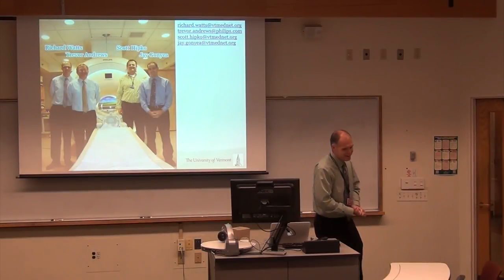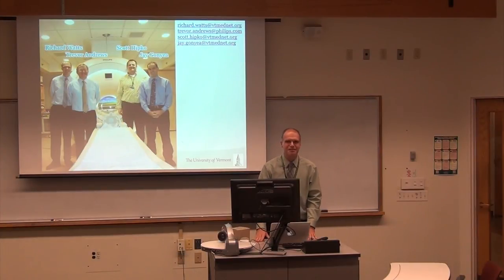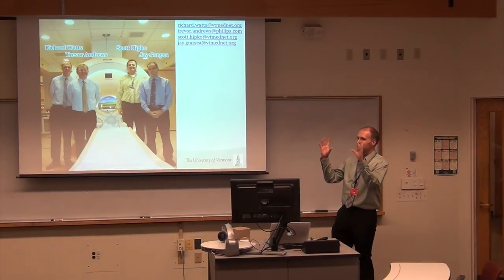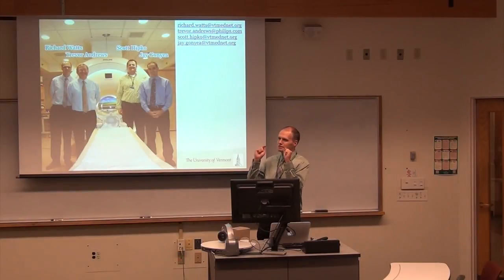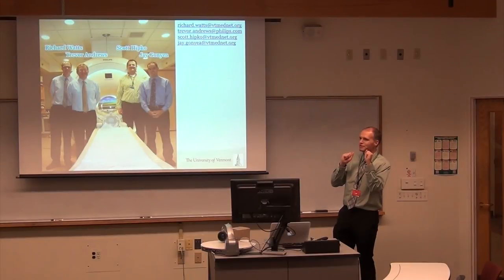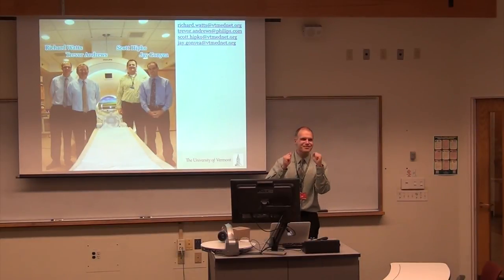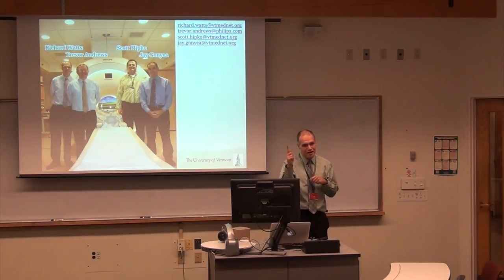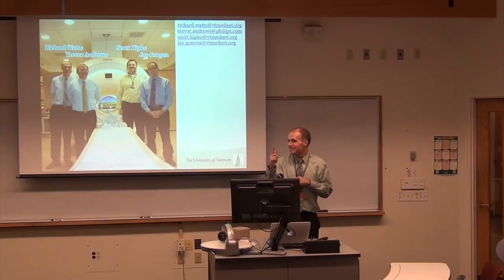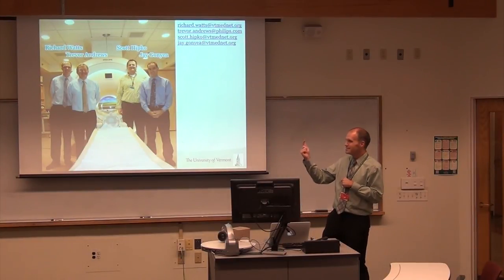Good question. Anybody who's sat in an MRI scan knows they are incredibly noisy. Actually our scanner can easily hit 130 decibels, which is very, very noisy. There are no moving parts in our MRI scanner - no moving parts. What do we have in an MRI scanner? We have a big magnetic field, and we have 3 gradient coils. We switch current through these 3 gradient coils very rapidly. What happens when you put a current through a wire in a magnetic field? You generate a Lorentz force. That's what you're hearing in your MRI scanner - the wires rattling around like this. Those forces are huge, because you're switching 20 amps in a millisecond, and it's sat in a 3 Tesla magnetic field. Forces are enormous, and that's the noise.